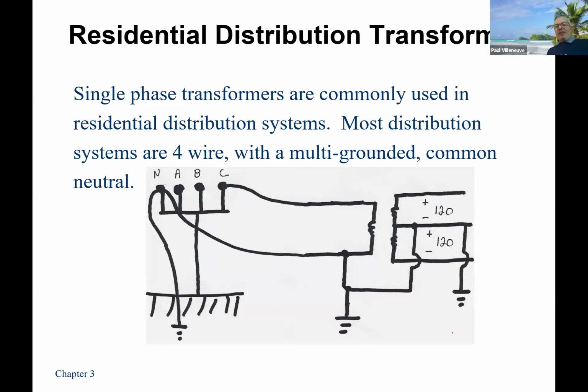So this is the last topic of our transformers for residents. Remember we talked about what goes in your house? So in your house, you just have a single phase transformer, and you can pick any phase you want, or you can pick any 2 phases. Most of the transformers that you'll see, they'll be single phase from phase to neutral, but sometimes you run them across 2 phases if you want. You just have to change the primary rating of the machine. I mean, the primary voltage of the transformer.